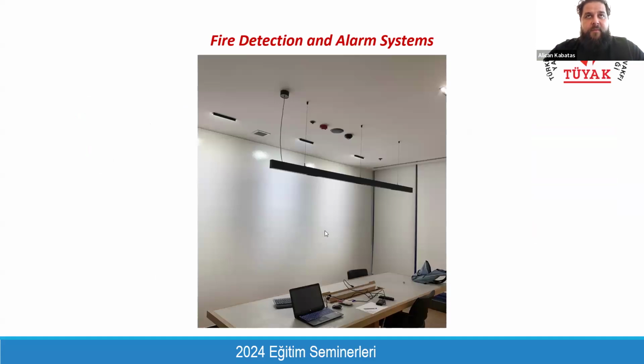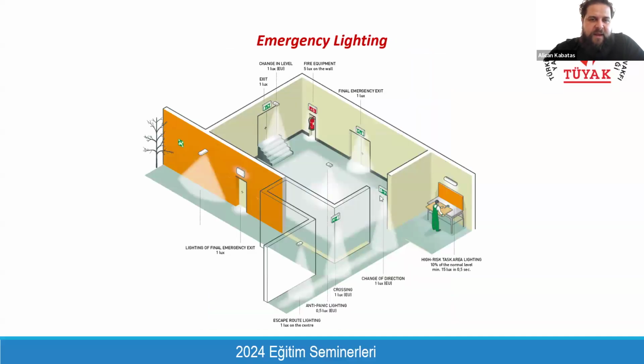And this is the room now I am making my presentation to you. We made it as an example. We have a spot type fire detector. We have a speaker, we have a visual alarm system, and we have a sprinkler system. And they are all coordinated on the same line, so this is done by the architectural team, and they are defining the locations. And as you can see, since we don't have a 1 meter parapet in the facade of our building, we have a closely located facade protection sprinkler as well. Even if we don't need it by distance, it is provided because of Turkish Fire Code requirements.